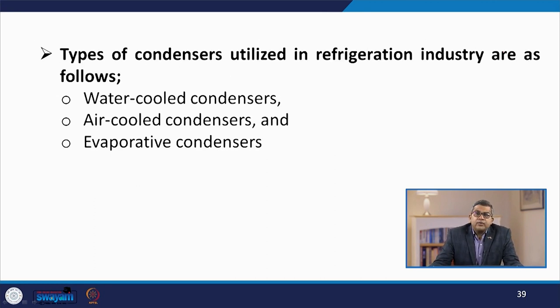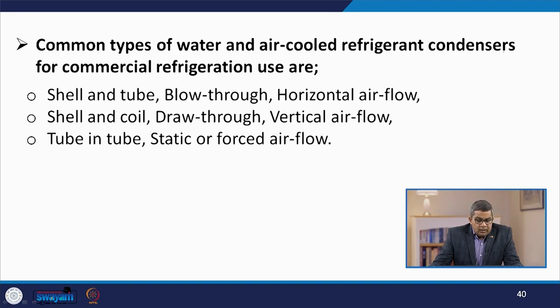The three main types of condensers used in the refrigeration industry are water-cooled, air-cooled, and evaporative condensers. Common types include shell and tube (blow-through, horizontal air flow), shell and coil (draw-through, vertical air flow), and tube-in-tube (static or forced air flow). Condenser selection depends largely on the size of the cooling load, type of refrigerant used, quality and temperature of available cooling water, and the amount of water that can be circulated.